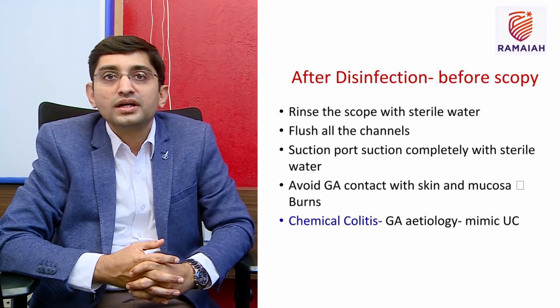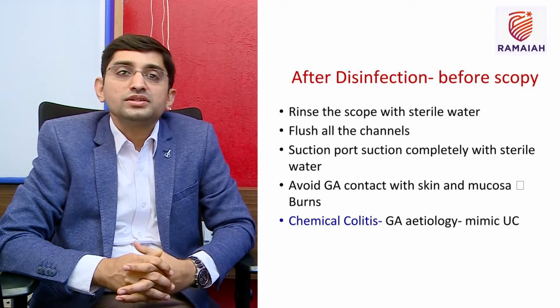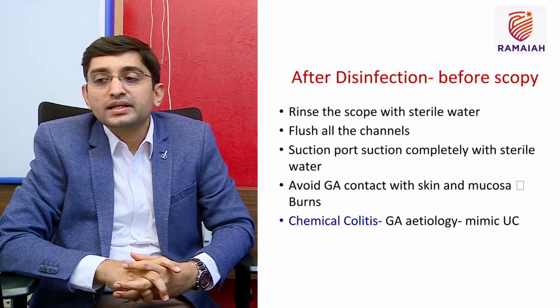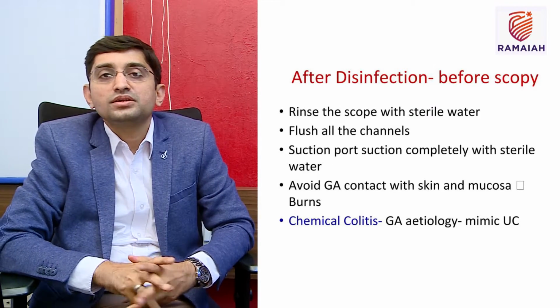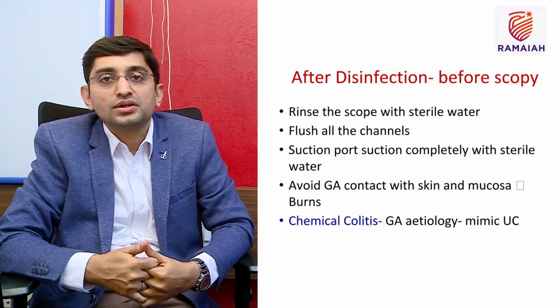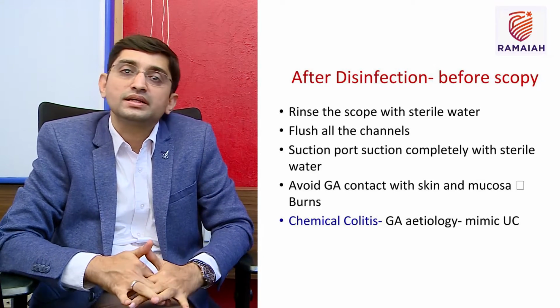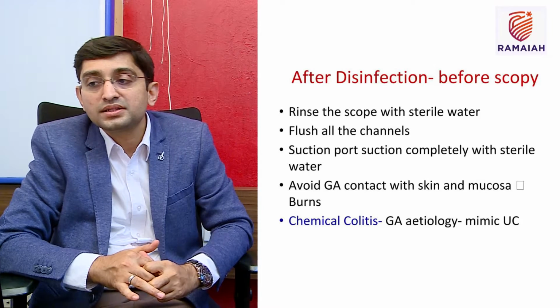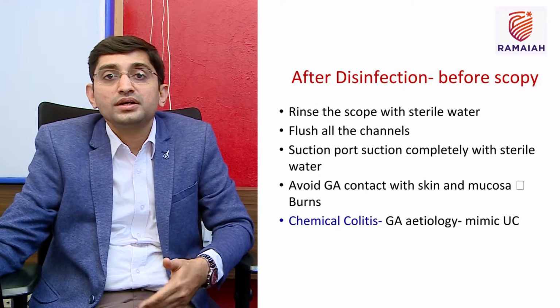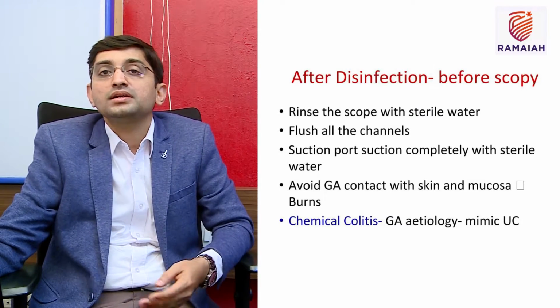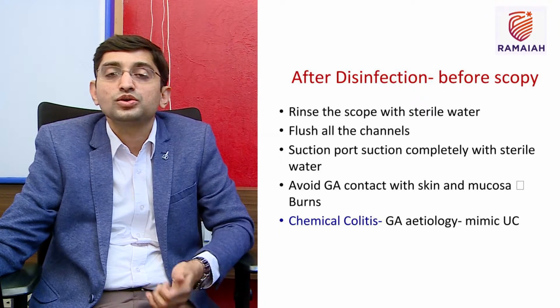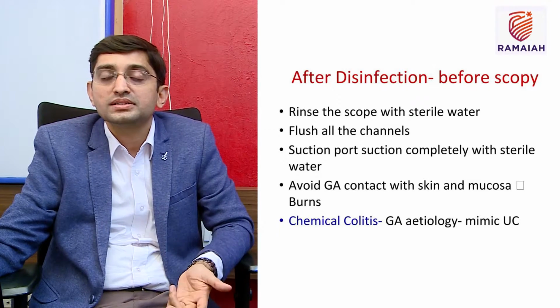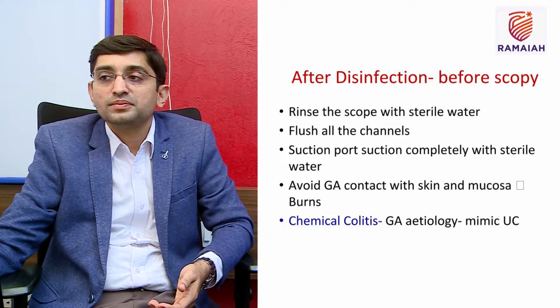Avoid glutaraldehyde contact with the skin and mucosa, because whenever there is contact with glutaraldehyde, there is a chance of chemical colitis. Glutaraldehyde is an aldehyde, and at 2% or 5% it is strong and can cause mucosal ulceration, and it can mimic ulcerative colitis during follow-up. So we should ensure that there is no glutaraldehyde within the scope, in the air, water or suction port. All three channels we should be checking.